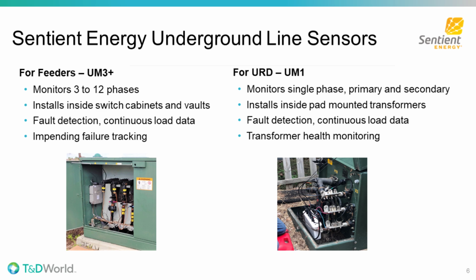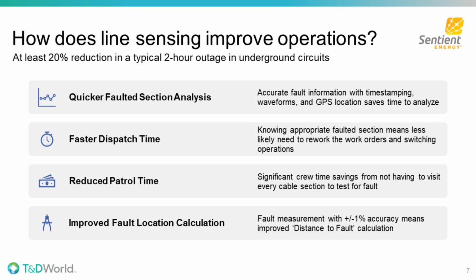You mentioned something about fault location. Does Sentient Sensor actually improve fault location compared with other incumbent processes that somebody might use? Yes, absolutely. I'm going to switch back to the slide we were looking at. Without sensors, you are relying just on the substation data, the breaker data and static models, where you're guesstimating locations to be patrolled, and your models can show up like 5 different areas to patrol. What we are seeing is that with the GPS lat long from the sensors, the waveforms and the high accuracy fault magnitude, you are able to input that data into your fault location calculation to have a more precise fault location calculation done and direct your crews the first time to the right areas to patrol.